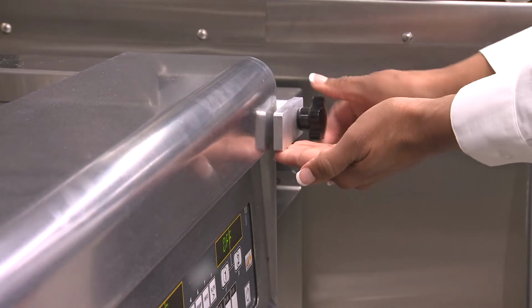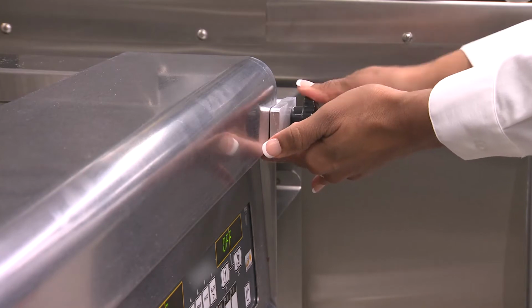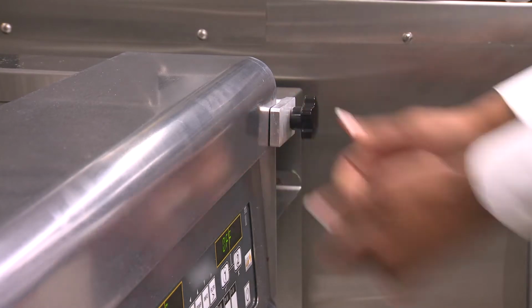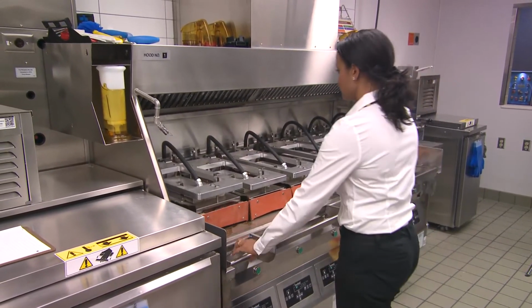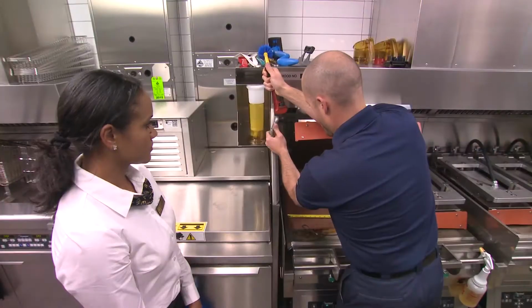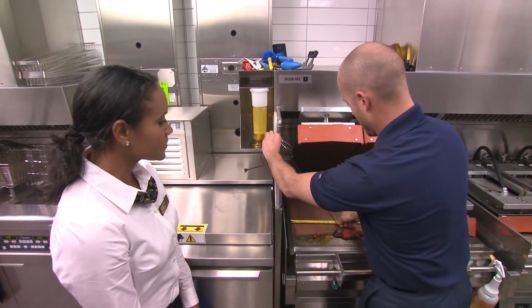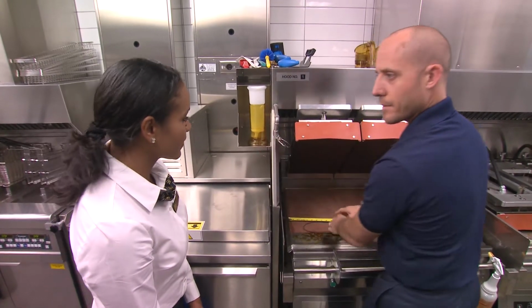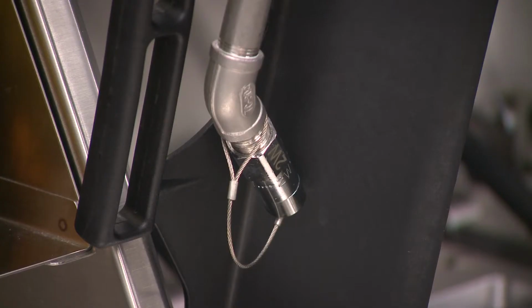Securing cooking equipment after servicing or cleaning will help ensure the fire system nozzle is positioned correctly in relation to the appliance cooking surface. Instruct all cooking and cleaning staff to avoid hitting or moving nozzles when pulling out cooking equipment for cleaning and servicing. Potential concerns with nozzle alignment should be reported and immediately inspected by your local authorized Ansul distributor. Also, keep pots, pans, utensils, and cooking materials from blocking the spray pattern of fire suppression system nozzles.